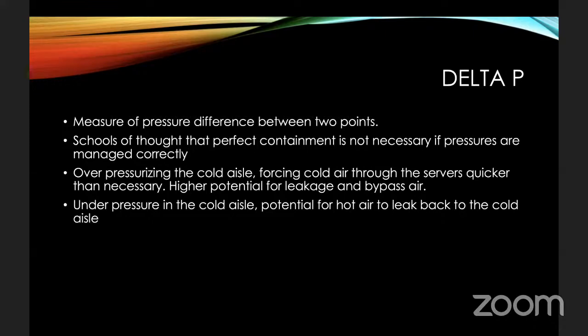Now, everything always flows from areas of high pressure to low pressure. If you blow up a balloon, you're increasing the pressure inside of that balloon. When you pop that balloon, the air escapes because it wants to balance the pressure. It wants to go from an area of high pressure to an area of low pressure. Therefore, it is physically impossible for the hot air to enter the cold aisle if the cold aisle is at a higher pressure than the hot aisle.